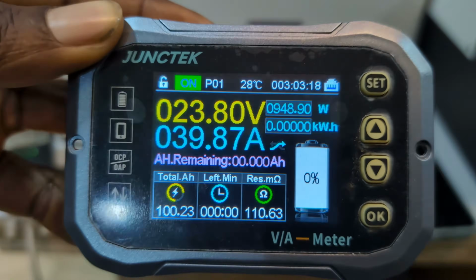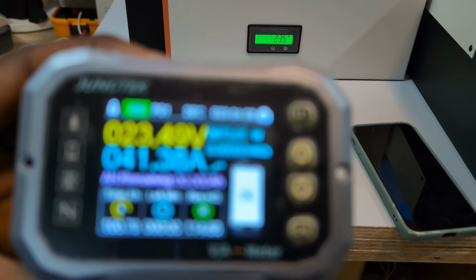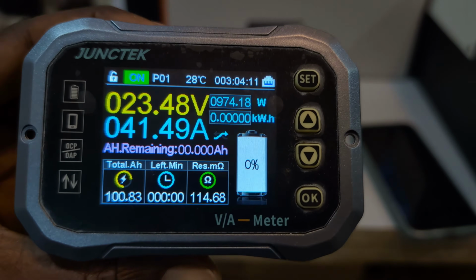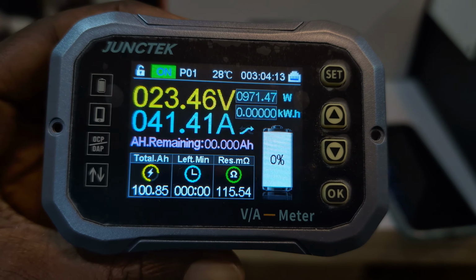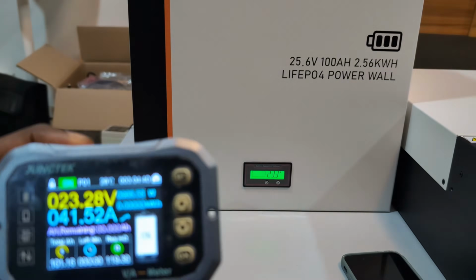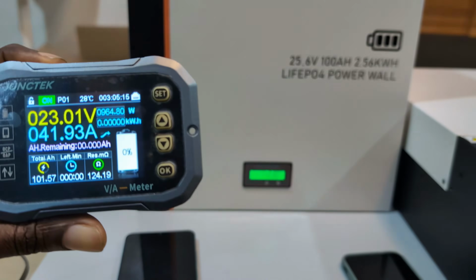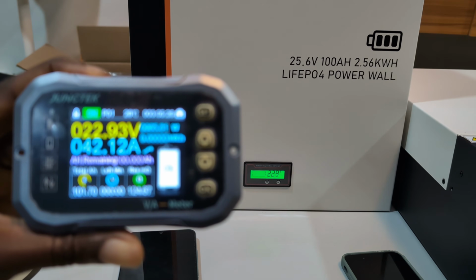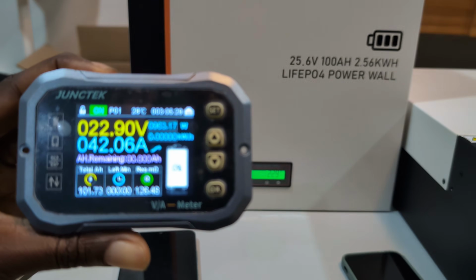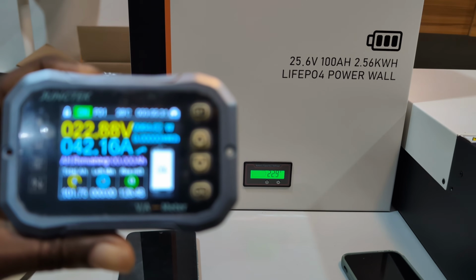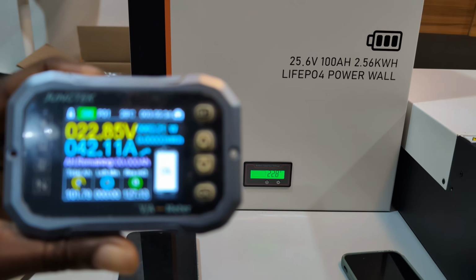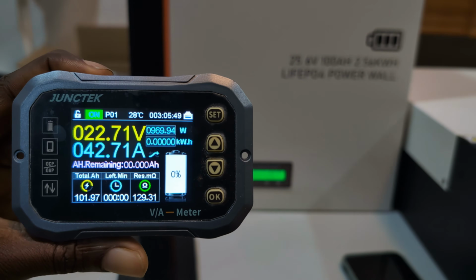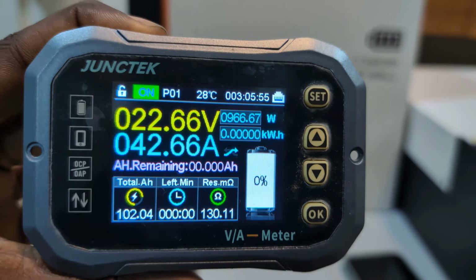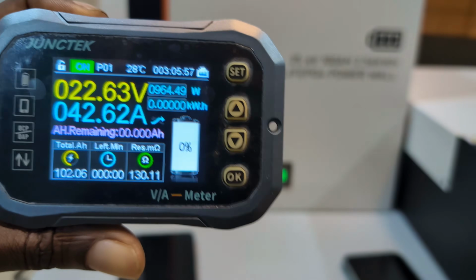Wow, that is interesting. So that's 23.5 on our battery, and here we have done over 100 amp hours, 101.5. Okay, now we are at 23 volts, so you can see the rate at which the battery drops from 24 volts to 22. There's no point, so cut off your battery at 24 volts. 102 amp hours. You can see 102 amp hours, 22.6. The battery is yet to shut down.